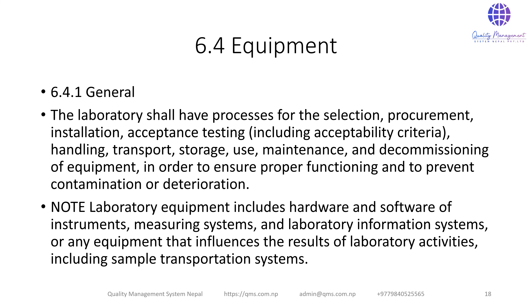6.4 Equipment — 6.4.1 General: The laboratory shall have processes for the selection, procurement, installation, acceptance testing including acceptability criteria, handling, transport, storage, use, maintenance, and decommissioning of equipment in order to ensure proper functioning and to prevent contamination or deterioration. Laboratory equipment includes hardware and software of instruments, measuring systems, laboratory information systems, or any equipment that influences the results of laboratory activities, including sample transportation systems.